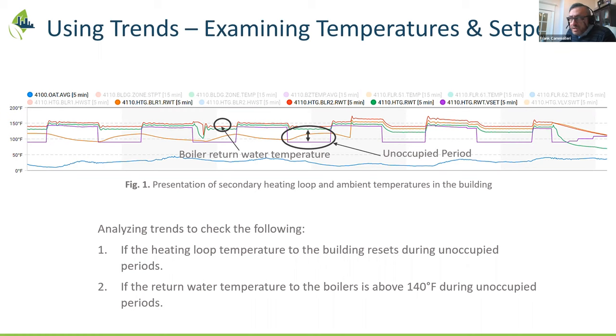And if the return water temperature to the boilers is in an operable region, we want to make sure it doesn't damage the boiler. Energy efficiency should never compromise the integrity of the equipment. So ensuring that the return water temperature is above 140.